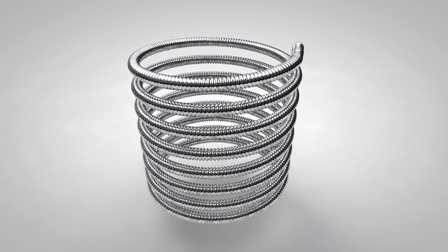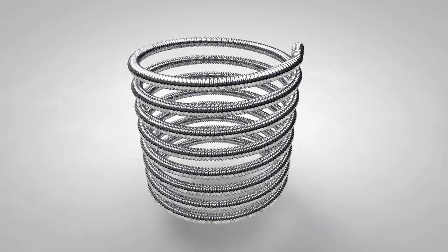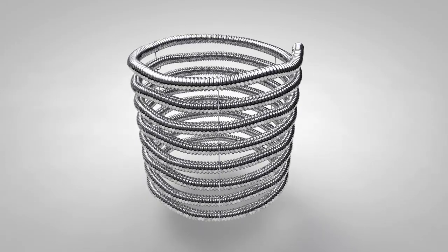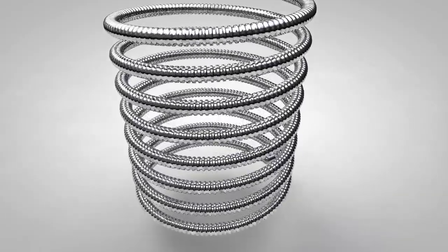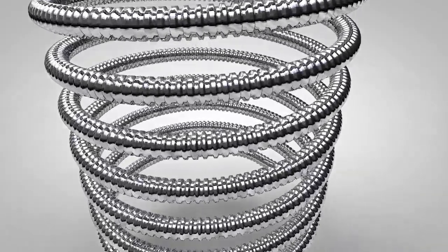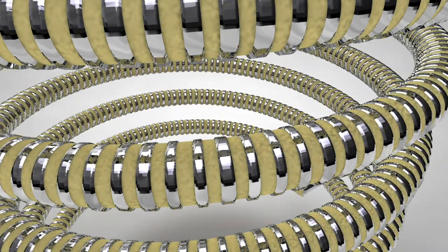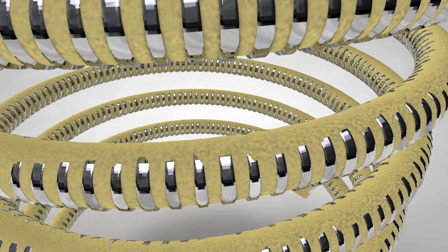However, the pipe is intrinsically flimsy and will shake about inside the cylinder even when supported by clips, making the coil more prone to leaks. The ridges can create turbulence resulting in noise and reduced flow rates, as well as trapping limescale leading to reduced heat transfer over time.